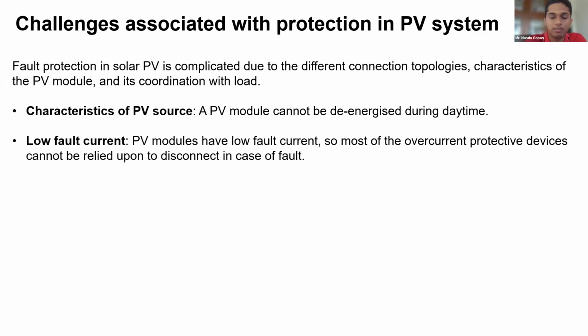Yes, in a PV system, even if there is a fault, an overcurrent protective device won't trip faster, because the fault current which comes in case of a fault will be really low. So an overcurrent protective device cannot be relied on in case of a fault in a PV system.